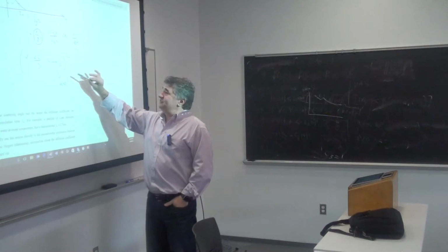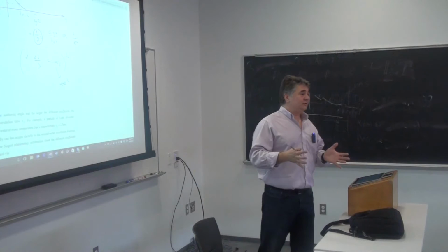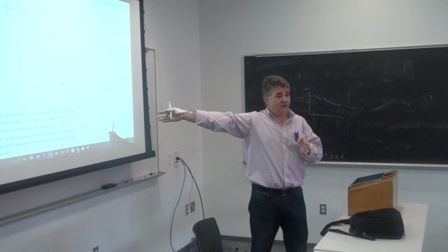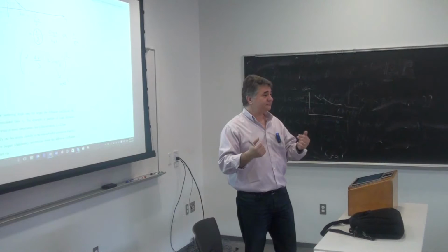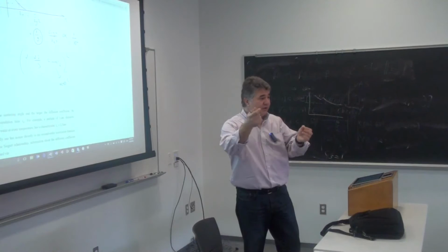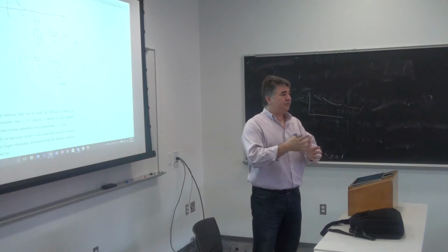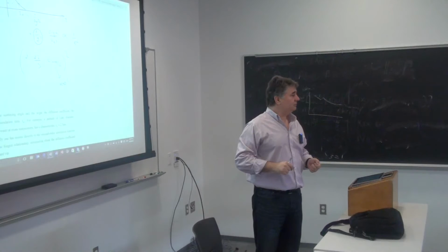So this is a very slow process. Your detector is going to be filled up with noise at those frequencies, right? But now, if I'm switching my angle to very high values, the same process looks to me as if it's faster. And the opposite is true. I have very tiny particles, very fast. They're beyond the frequencies that I can measure with my detector. I'm closing down my scattering angle, and I'm bringing them into my measurement range. Very useful.